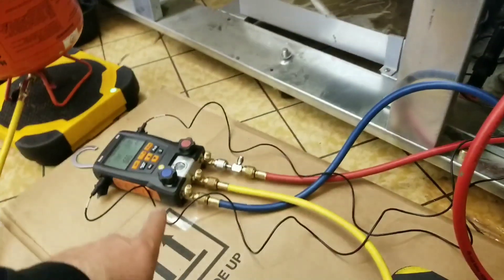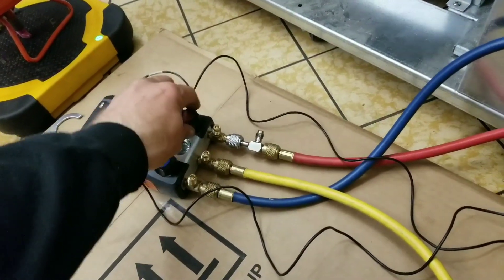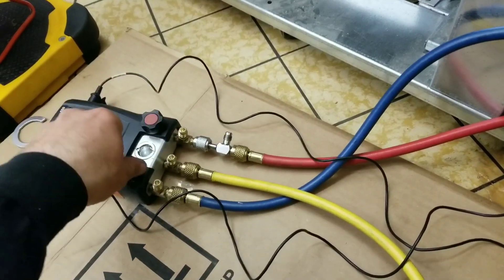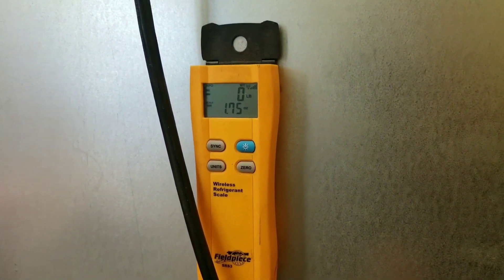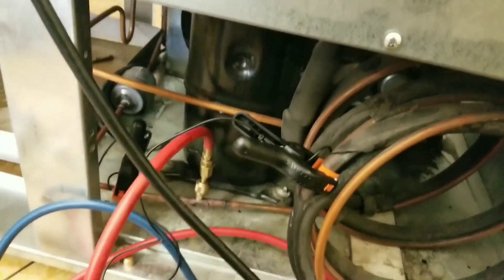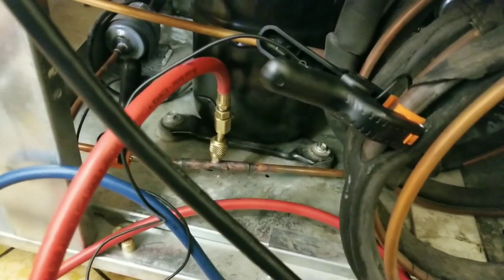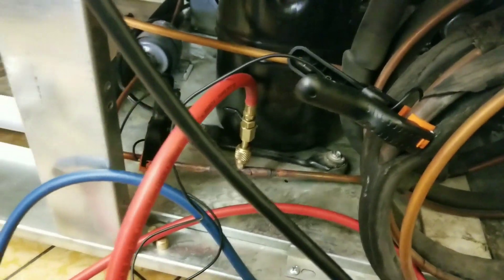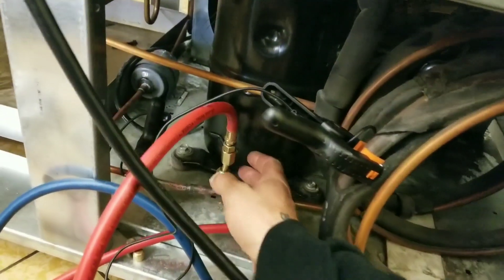So right now my manifold set is full of refrigerant all the way up to my service ports. My entire gauge set, hoses and everything, took about 2 ounces of refrigerant. So I'm going to go ahead and zero that out. Then I'm going to weigh in my charge, which is 3 pounds 6 ounces - 54 ounces altogether - 3 pounds 10 ounces right into my high side.